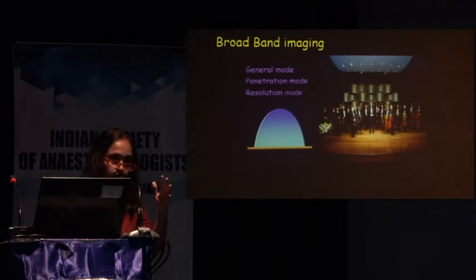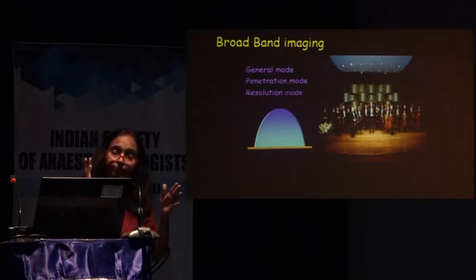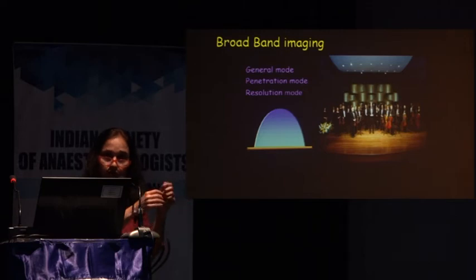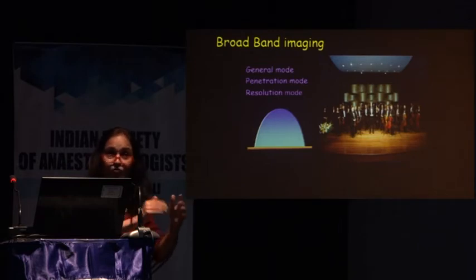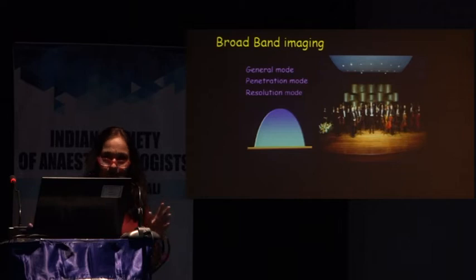Don't go to resolution. I'll tell you how to pick up resolution in the same. So you will have certain knob on the machine. You have to choose either the general mode. So choose your general mode and see if the image is good in this particular situation. Now come to penetration mode. Out of the 7 to 13, ask for the lower ones. So the ultrasound image is going to be better if you ask penetration, if you are using a linear probe for deeper structures. Am I confusing you? All right, yes?